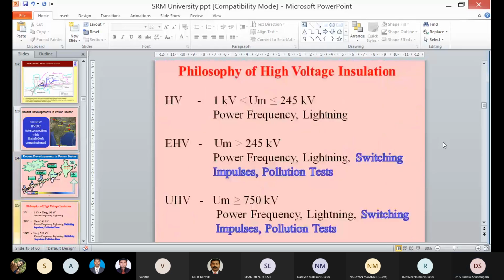So when it comes to the philosophy of high voltage insulation, the classification I have shown here is high voltage, extra high voltage, and ultra high voltage. It is as per IEC standard 60071. Please note down the number, because when we are speaking about specific terms and specific categories, it is really important to know the standard pertaining to the levels and how the calculations are made. I'll be showing a few calculations from the standard, and how to calculate, I'll also be discussing in this presentation. So the classification is as per IEC 60071.